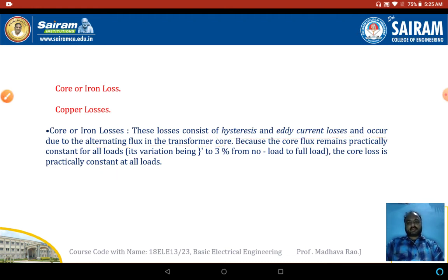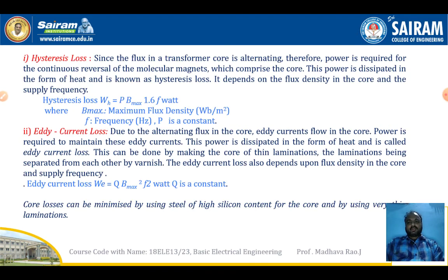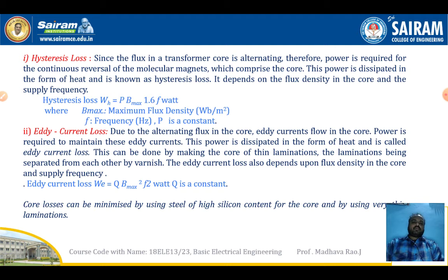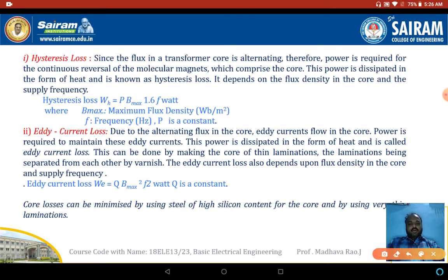Due to alternating flux in the transformer core, hysteresis losses occur. Some power is required for the continuous reversal of the molecular magnets. To maintain this reversal of molecules of magnets, some power is required, and the power dissipated in the form of heat is known as hysteresis loss.